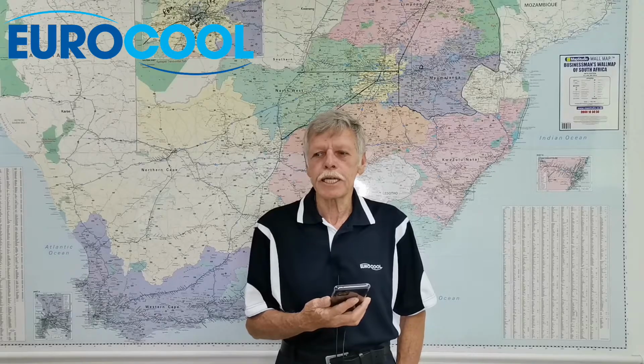If there is power, then you can look deeper, because the indoor communication data line is the only communication between the indoor and the outdoor, and that is telling the outdoor what function to perform. So make sure that you are getting power firstly on your outdoor PC board. If you're getting power on your outdoor PC board, then more than likely check that data line cable, where there might be a break inside the electrical cable which you're not aware of.